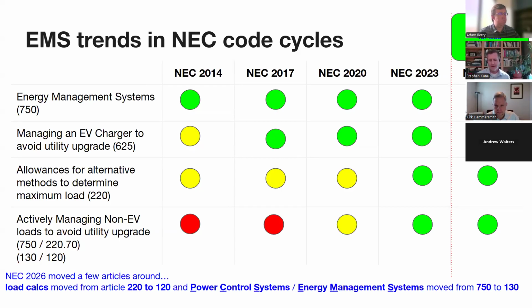A common use case we hear from customers and people in the field: a homeowner is excited because they bought an electric car. They come home wanting to install an EV charger, but they only have 100 amp service. Their electrician says they don't have enough capacity, so they need to trench up the yard or get a new aerial drop from the utility company and bump up to 200 amp service just to install a 30, 40, or 50 amp EV charger.